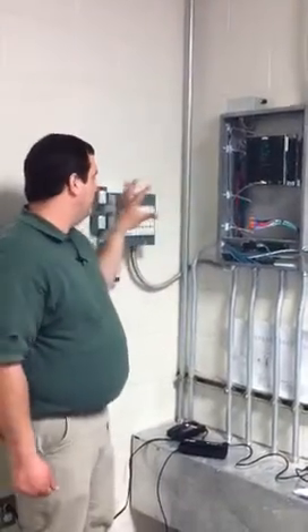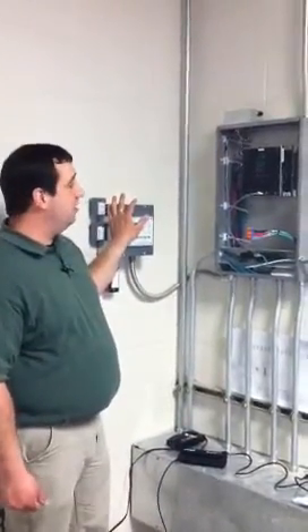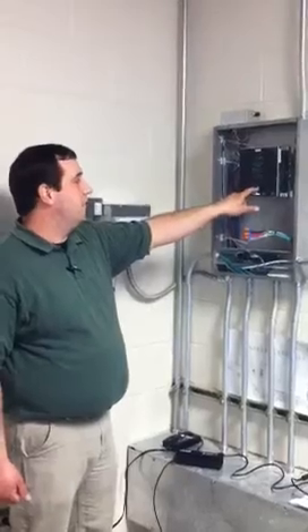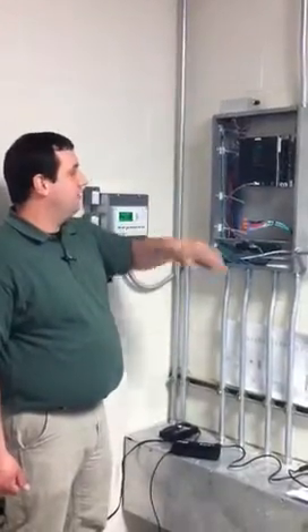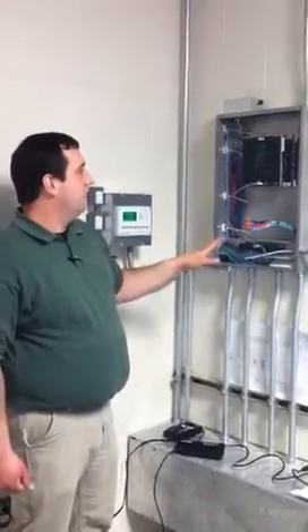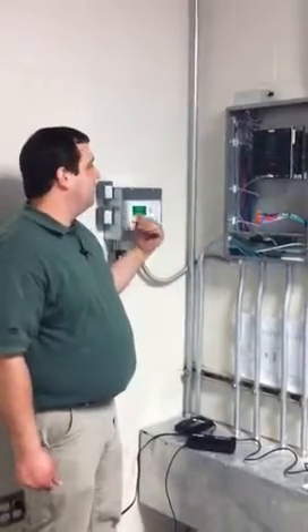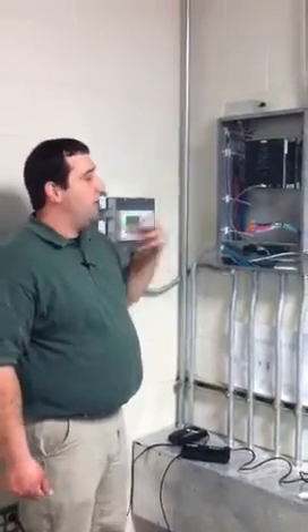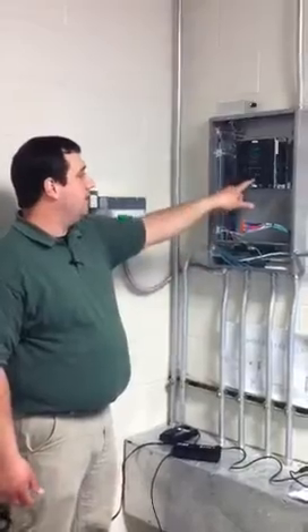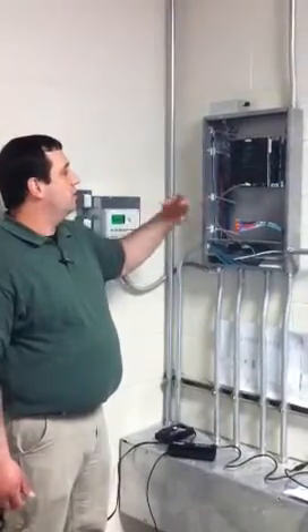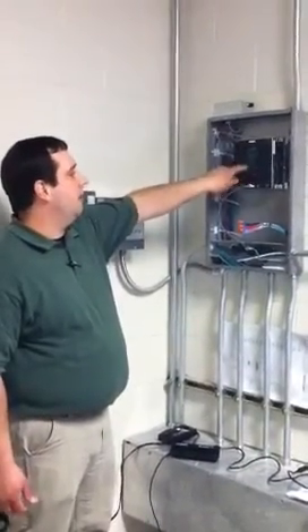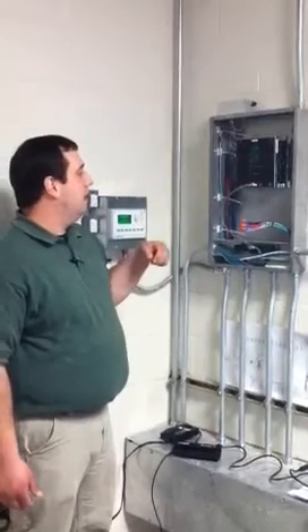If the processor or the brain of the system should fail, there is an override button. You hit the override button, it turns all the relays on to 100%, and the scheduler then basically is taken out of the equation. The only way to get the system out of override is to hit the override button again. You'll know the system's in override when the LED is blinking.